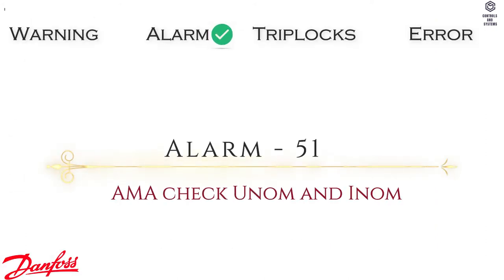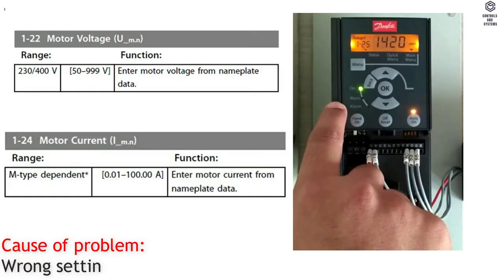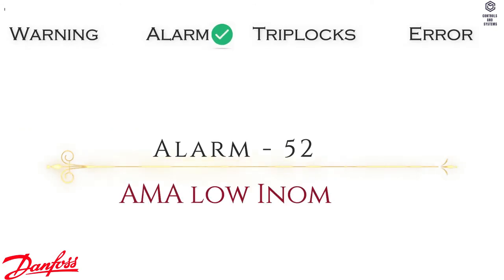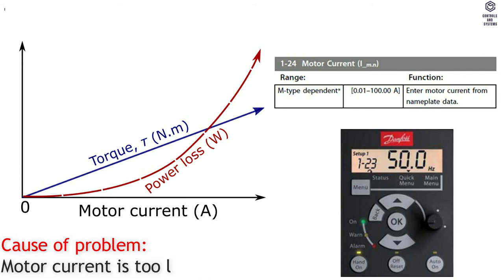Alarm 51: AMA Check Unom and Inom. Cause of Problem — wrong setting for motor voltage and/or motor current. Alarm 52: AMA Low Inom. Cause of Problem — motor current is too low. Check settings.